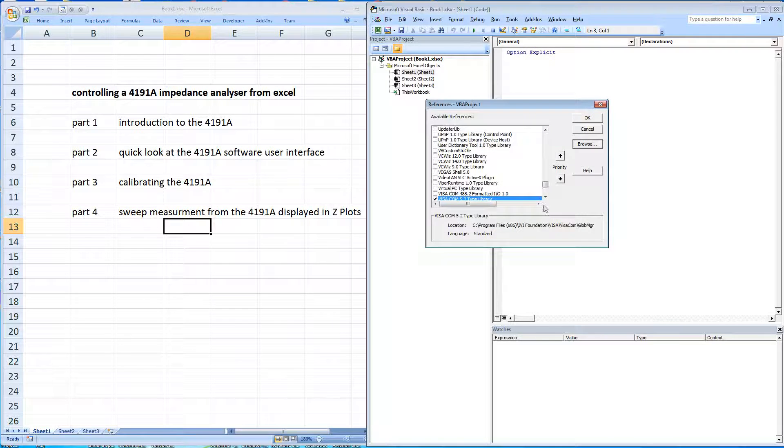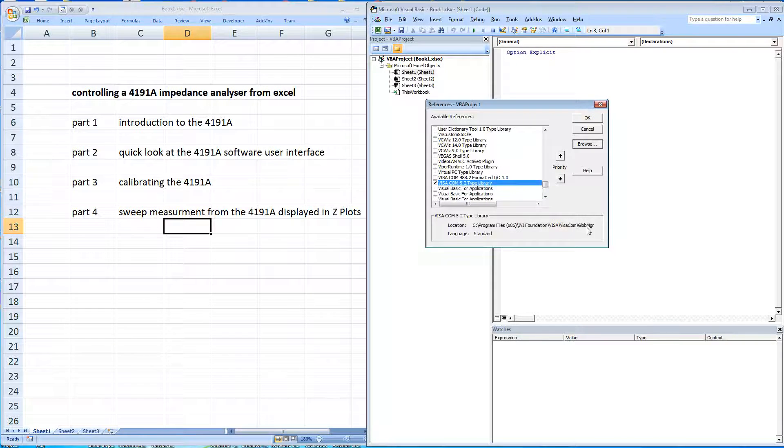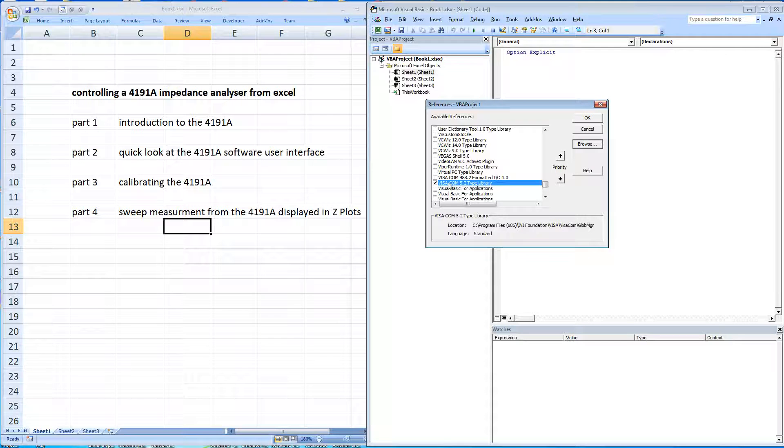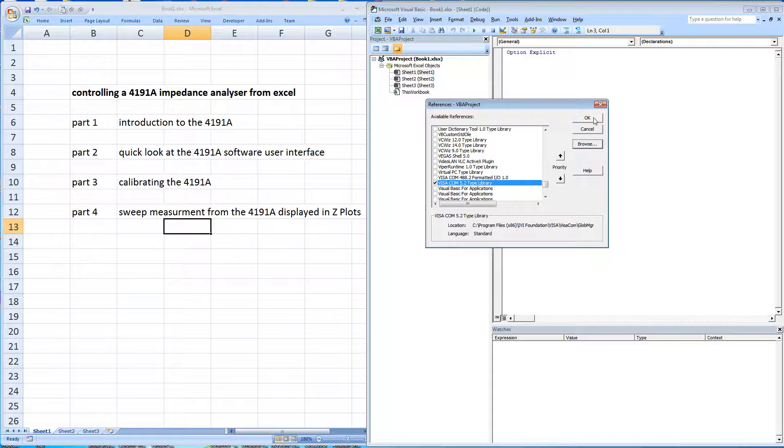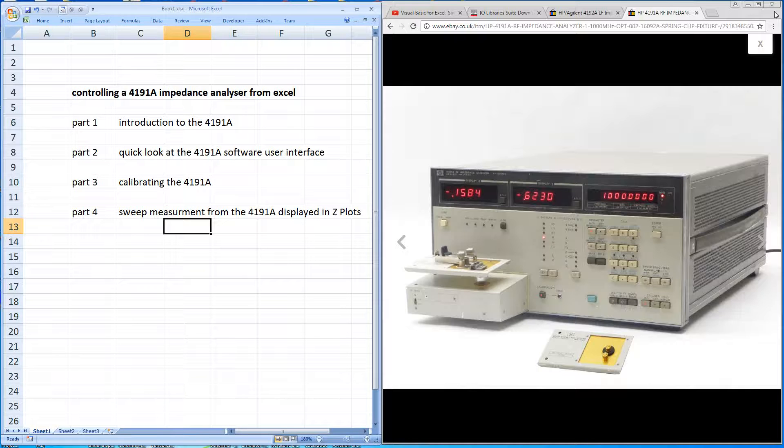OK. So you can see now we've got a reference and we've clicked to that. There's the program location. You do need to have this file as a reference within Excel for it to talk over GPIB. They're the two prerequisites to controlling instruments from within Excel.